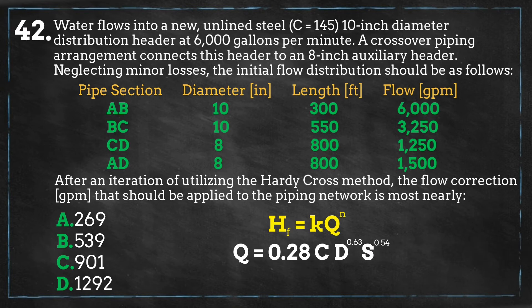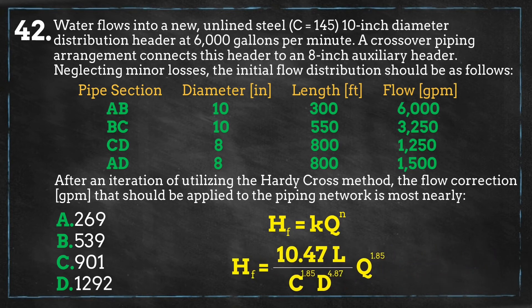Where d is the diameter of the pipe in inches. Head loss is calculated as the slope times the length of the pipe. Taking the Hazen-Williams equation, adjusting it to solve for the slope, and plugging it into the head loss equation gives the combined formula. The first portion of this equation represents the variable k. We can now plug in the information for each of the four sections of piping and get the values for each variable in the head loss equation.